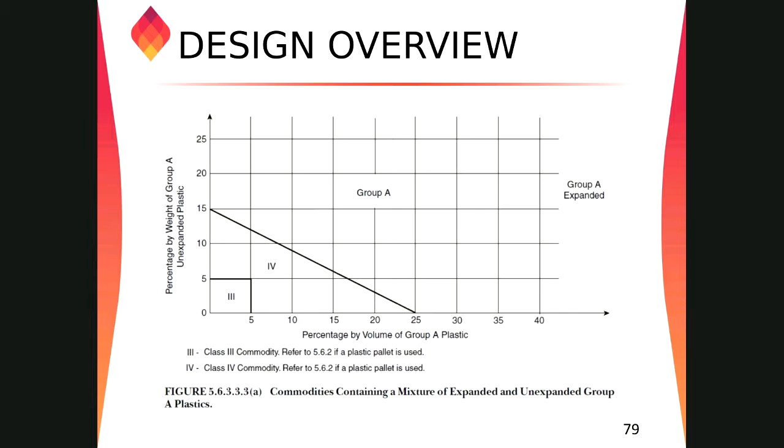You know why? Because if you know that your building is designed for a sprinkler system, most of the product in the building is only group 4 commodities, which is not as severe as the group A plastics. Now we want to put group A plastic into the same commodities. We have some channels that we can put that one. We cannot go more than 15% by unexpanded weight, or by 25% of the volume. We keep the limit into that. This is how they explain.